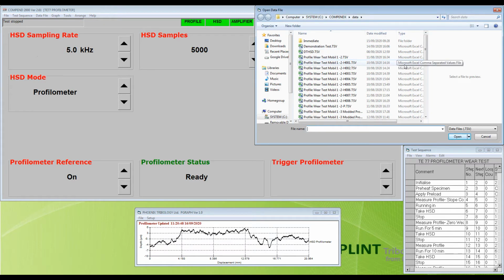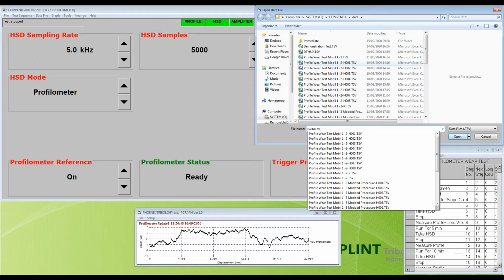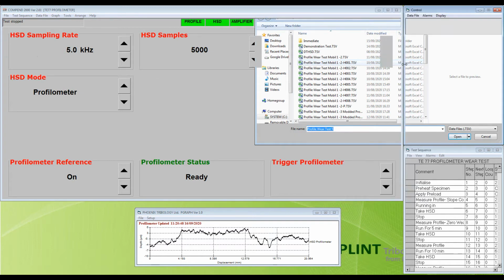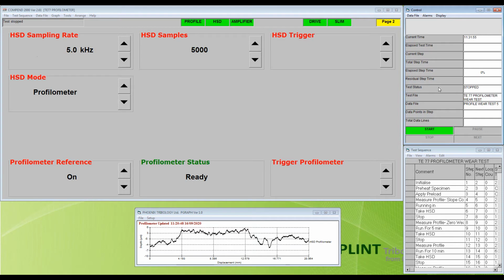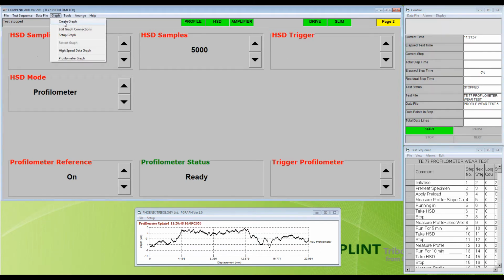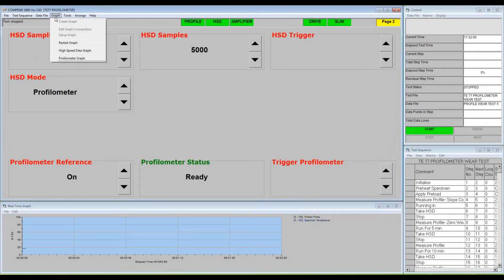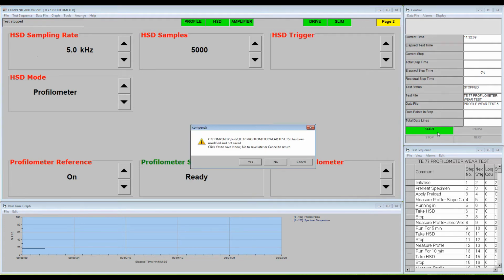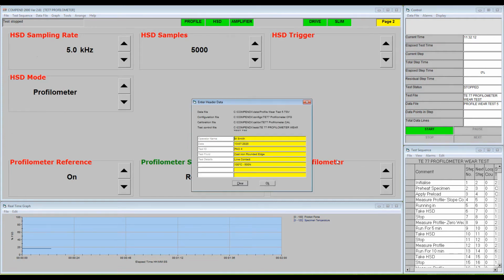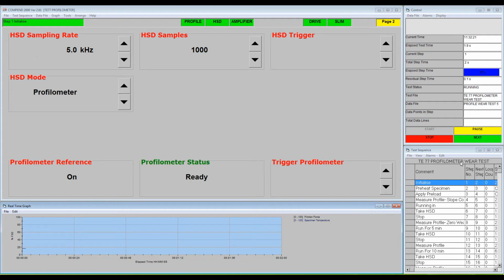Open a data file before running a test. A profilometer data file containing all the measurements taken during the test will automatically be created. The file will have the same name as the low-speed data file, followed by the suffix P. A hyperlink will be created in the data file each time a profile is measured. The three available on-screen graphs, low speed, high speed and profile, can be opened at the same time. Press Start to run the test.